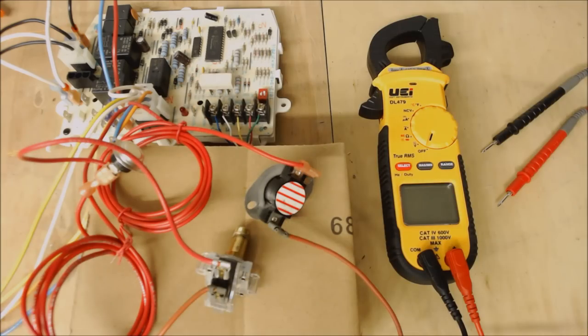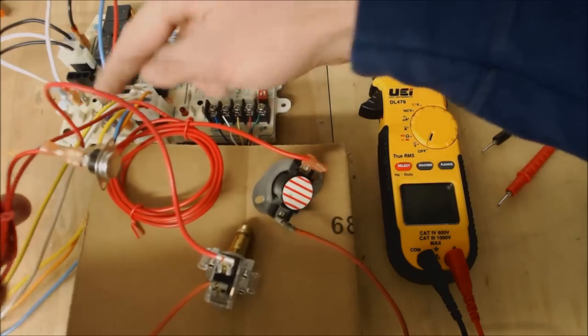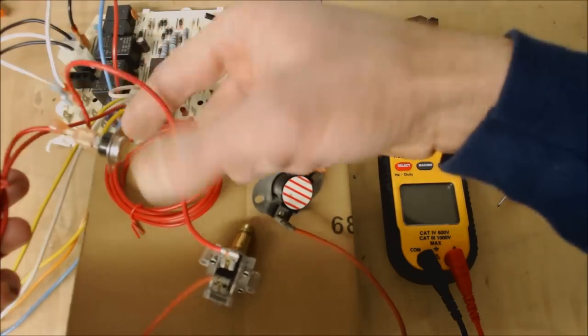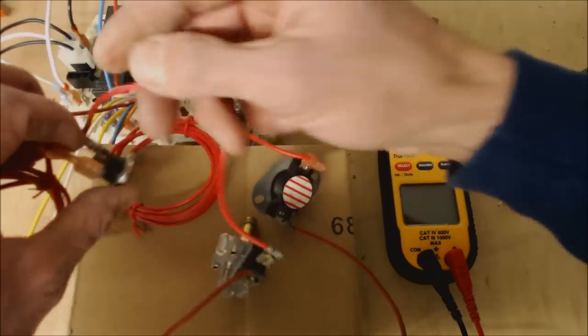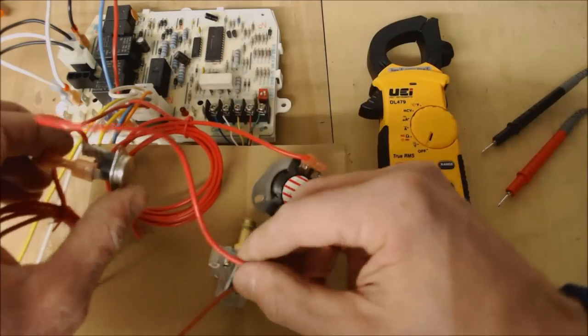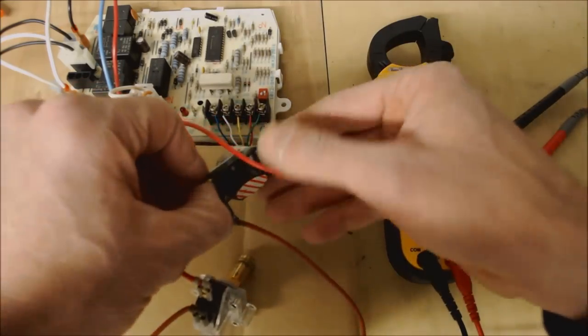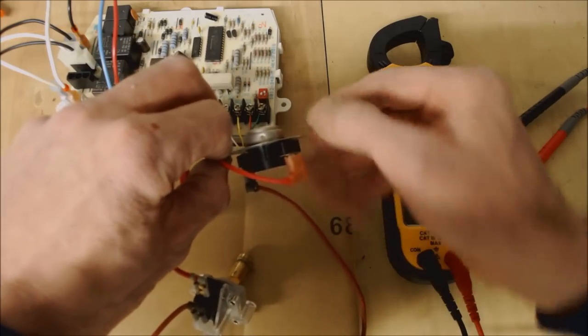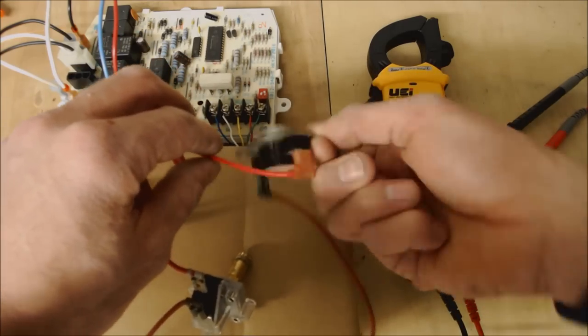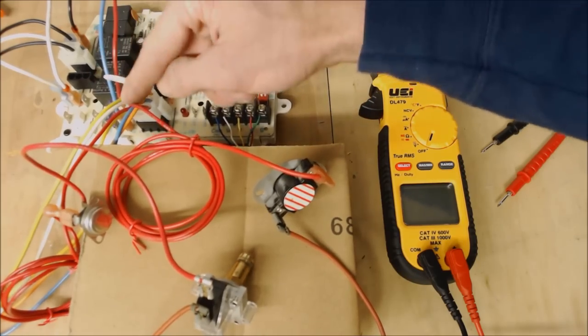Now, here's a quick example of safety wiring. Okay, so you have your plug right here. Your hot wire comes out, goes through this flame rollout switch right here. The power is off right now. Then it goes through the low-pressure gas switch. Then it goes through the high-heat plenum switch right here. So this is the high-heat temperature sensor. And then it goes back through into this plug again right here.